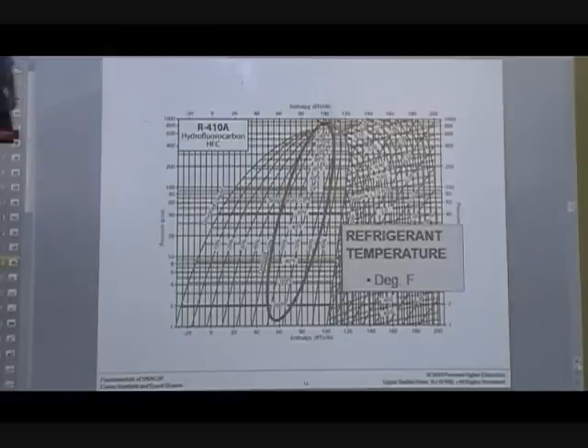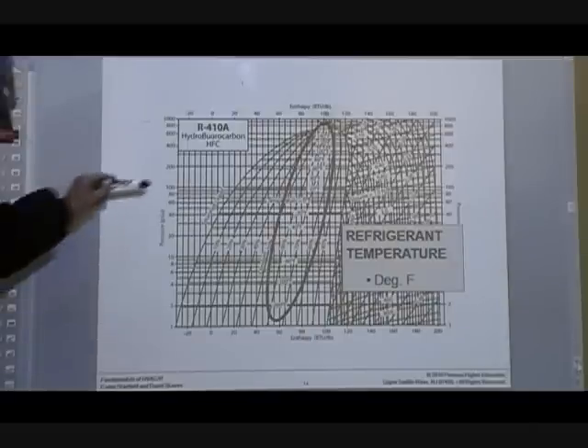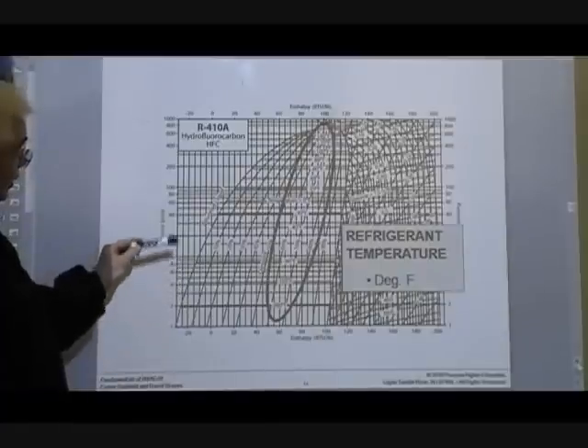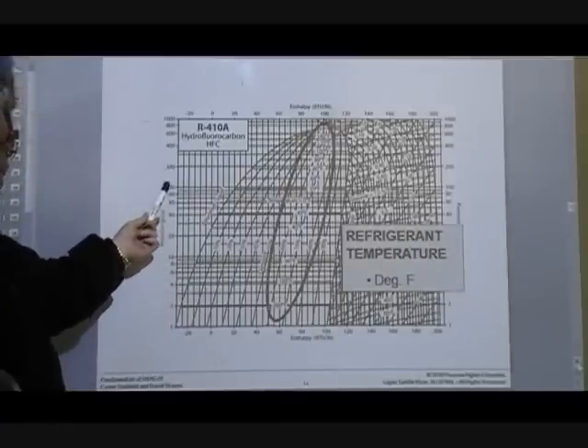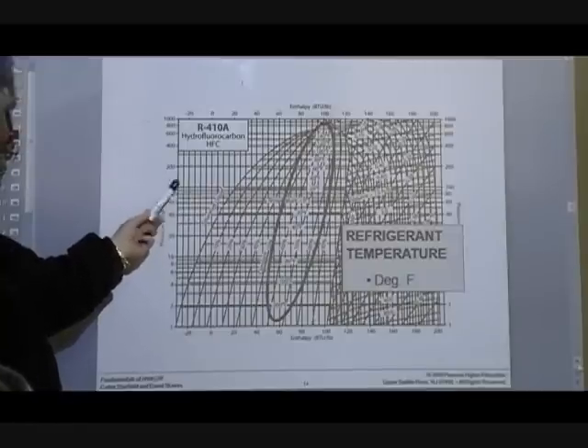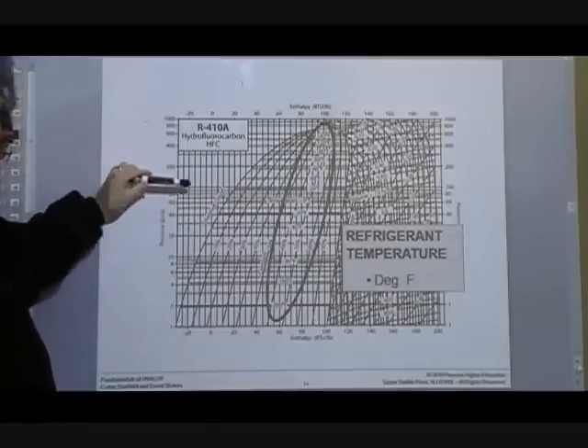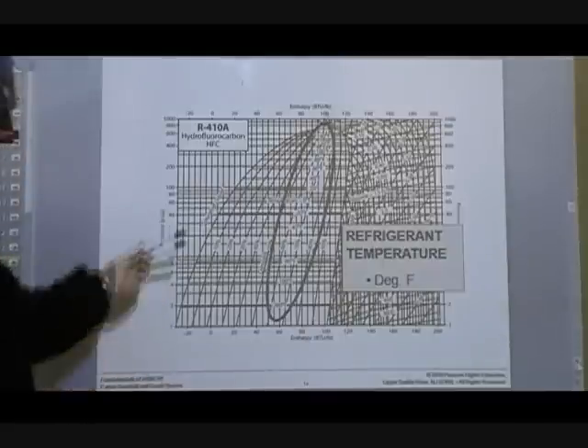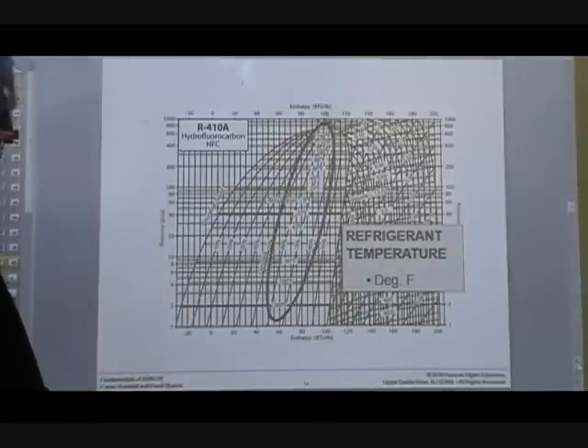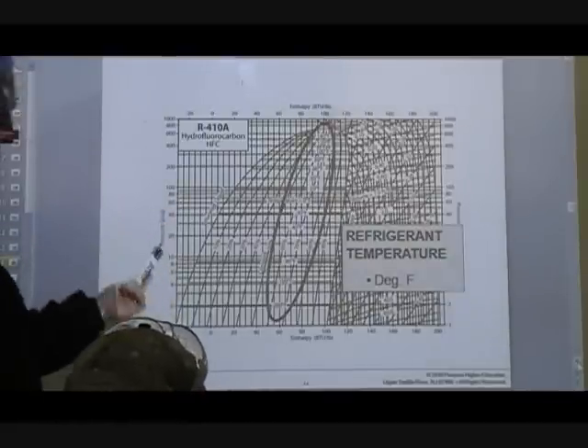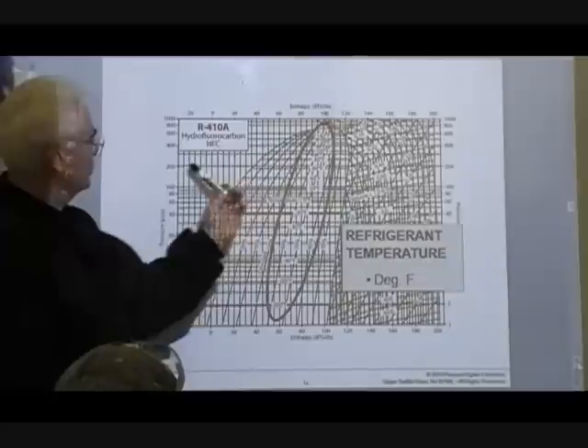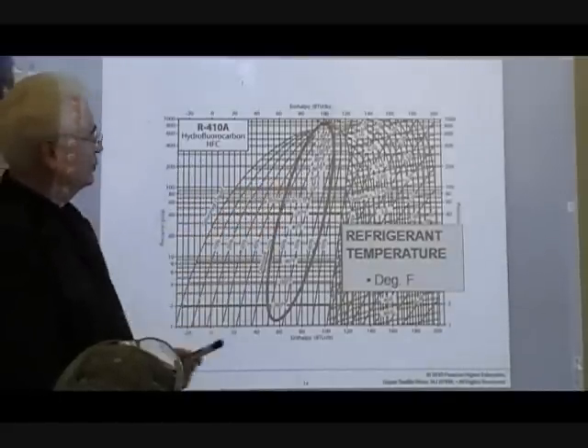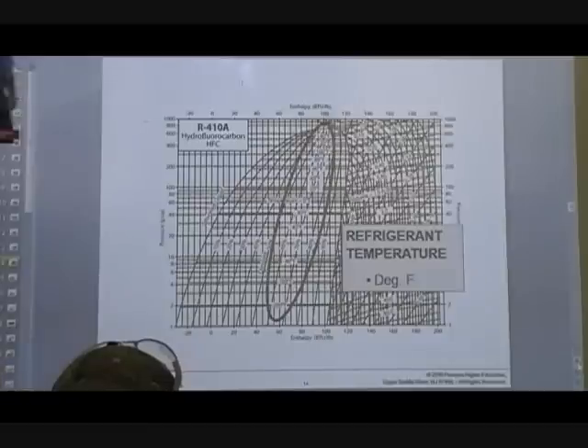Refrigerant temperature on the chart is just a conversion of your pressure and temperature. A regular pressure-temperature chart uses gauge pressure, not absolute pressure. This would not be a true pressure-temperature chart because this uses absolute pressure — you would have to convert that back to gauge pressure, and then your temperature would match up for your pressure-temperature diagram. Basically, the pressure-enthalpy diagram is sort of a pressure-temperature chart — you could use it as one, because your horizontal lines represent both pressure and temperature, since there's a direct correlation between the two.